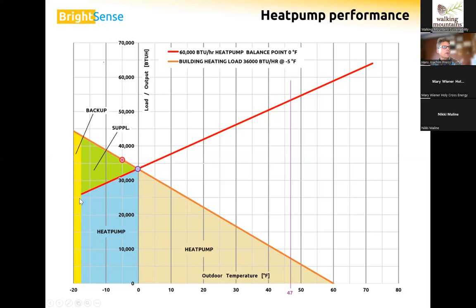I was assuming that the heat pump would operate down to negative 18. So at negative 18, if it gets colder than that, we would need to have a heat source that can produce 100% of the load of our home in this example. This is a little simplified. In reality, this is not a straight line because it depends on many other parameters. It depends on whether the heat pump is located against a south-facing wall, which is a little warmer. All these kinds of things play a little bit of a factor too, but for this example, this is what we're moving forward with.